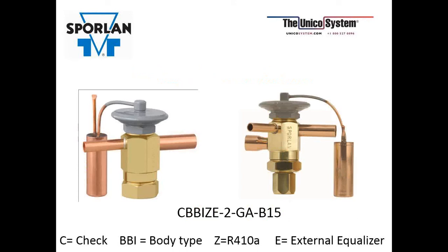Pictured here are a couple of common TEVs that Unico uses. Although I do have pictures with solder connections, they usually use a chatleff connection. The valve on the left is a non-adjustable version. You can notice the flat bottom and the 2-piece construction. It only has the valve body and the bottom cap. The valve on the right is adjustable. It has a 3-piece construction: the valve body, the bottom cap, and the adjustment seal cap. Underneath that seal cap is the adjustment stem.